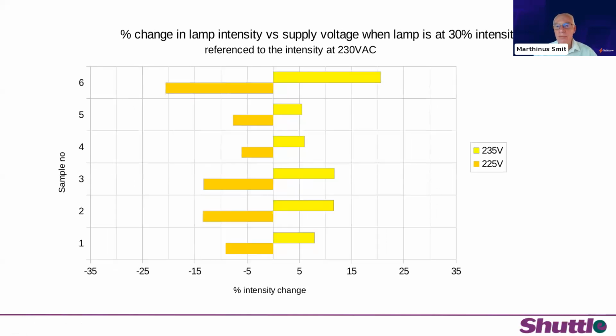Then if we dim down to 30% intensity with a trailing edge dimmer, we can see that the picture changes quite a lot. Most of the lamps exhibit at least a 5% change in intensity when you fluctuate the voltage from 230 to 225 or from 230 to 235 volts. Now, 5% when the lamp is at 30% intensity is quite visible, and you can see it with the naked eye.